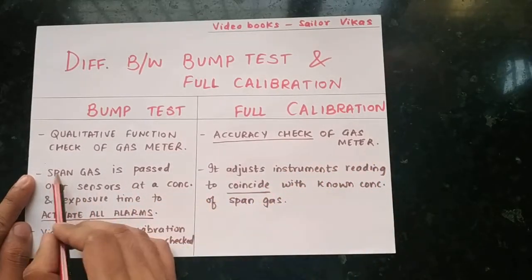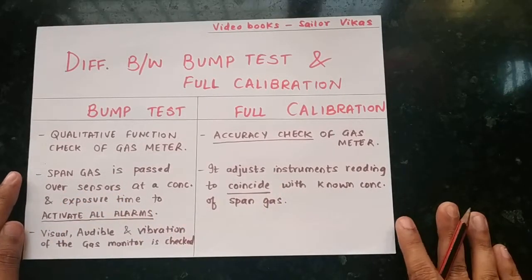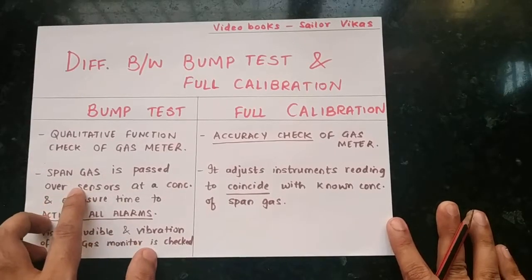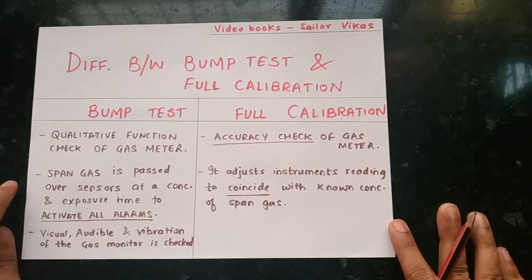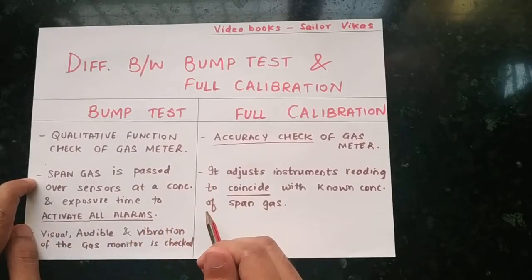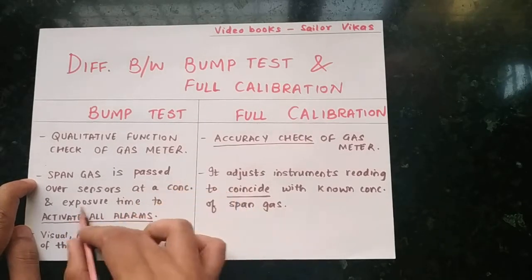In both cases, span gas is passed — here also span gas, and here also span gas — but the only difference is that in bump test, span gas is passed over the sensors at a concentration and exposure time sufficient to activate all alarms. The span gas bottle on board has a particular concentration, and when we pass this gas at that concentration for a particular exposure time, it will activate all the alarms of the gas meter.